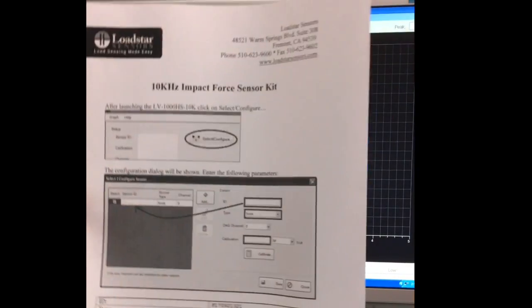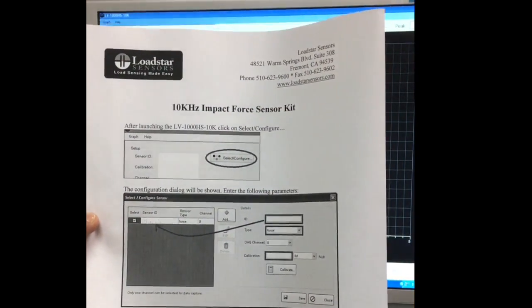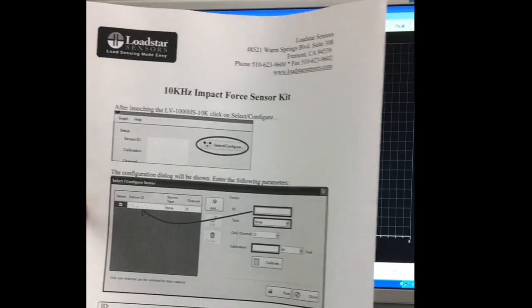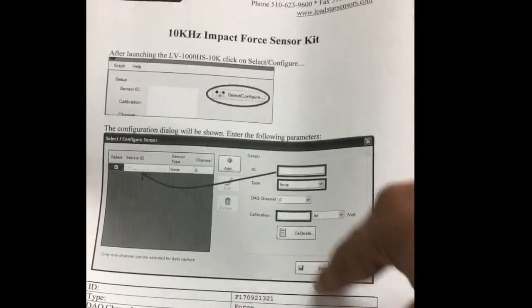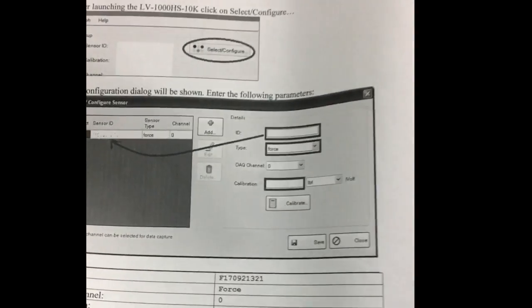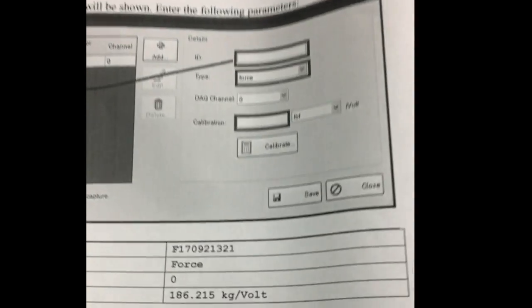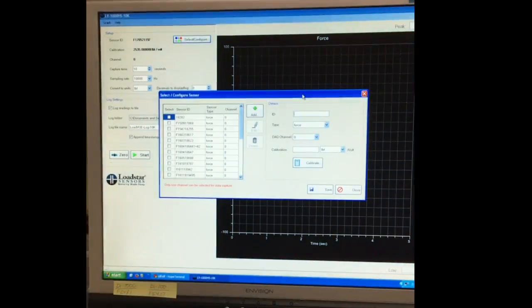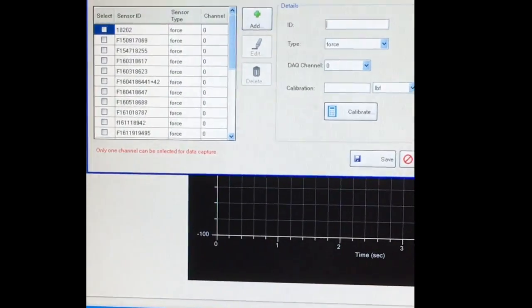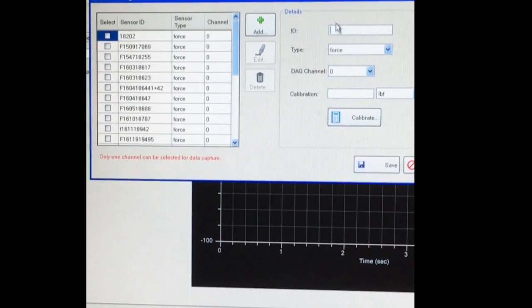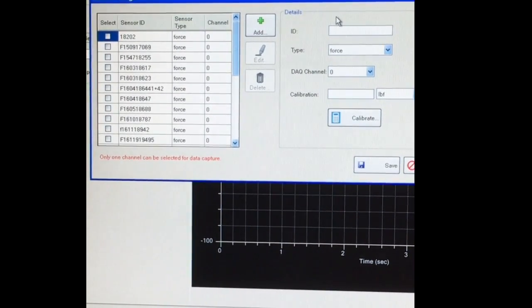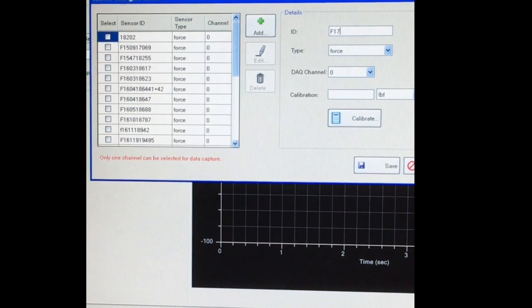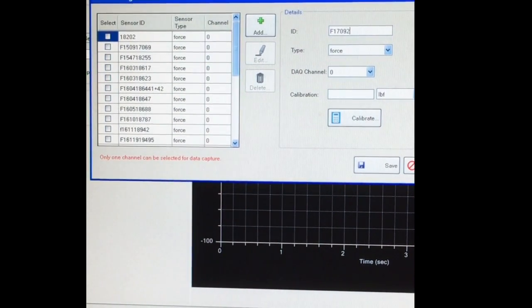Here is the actual copy of the cert that we include with the package where we tell you what the force per volt is. This is what we need to enter up here, so I'll call it F170921, the force type channel 0 calibration.